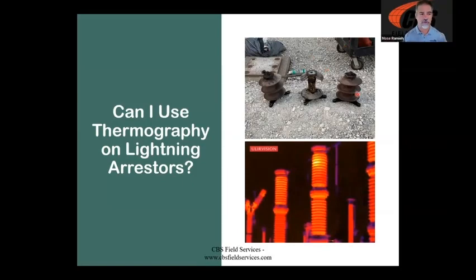And for the life of me, I couldn't find a picture that I remember taking years ago of an arrestor very similar to this that was failing. But here's an example that I was able to find. We can see a little bit of additional thermal energy right in this area of that arrestor, and that is a precursor to failure. So once again, if we have an arrestor that is above ambient temperature, that tells me that it's conducting in some fashion. Any conduction other than when there's a lightning strike is bad. So let's keep that in mind.